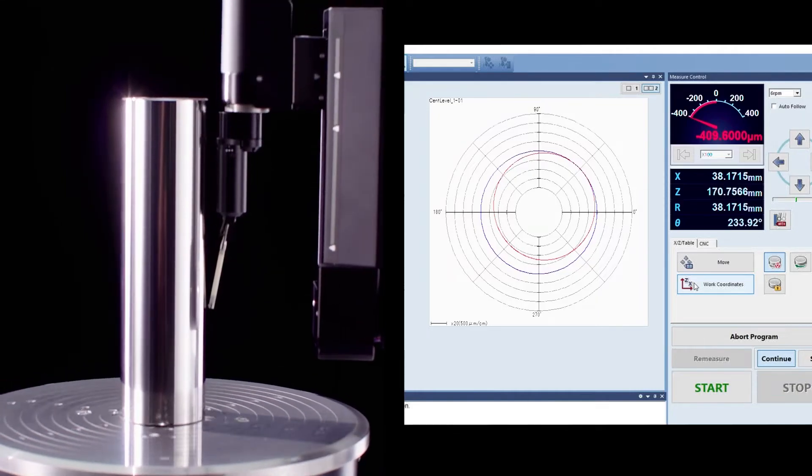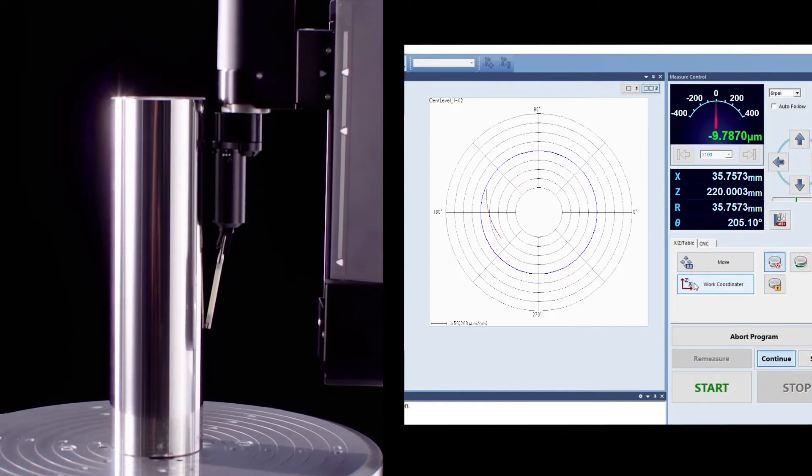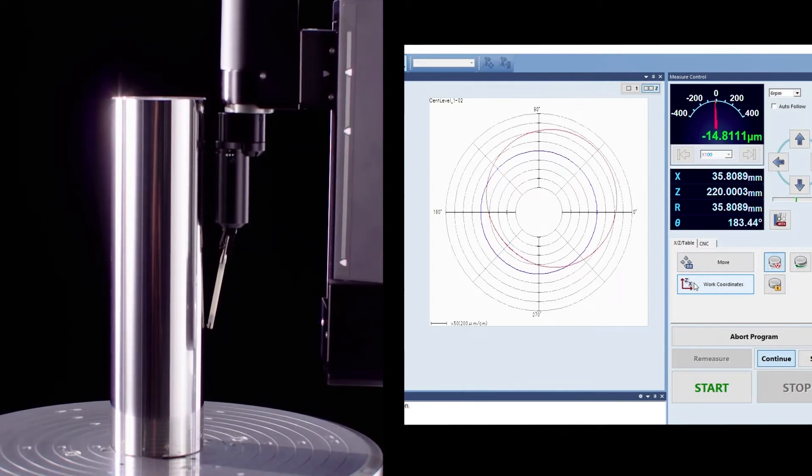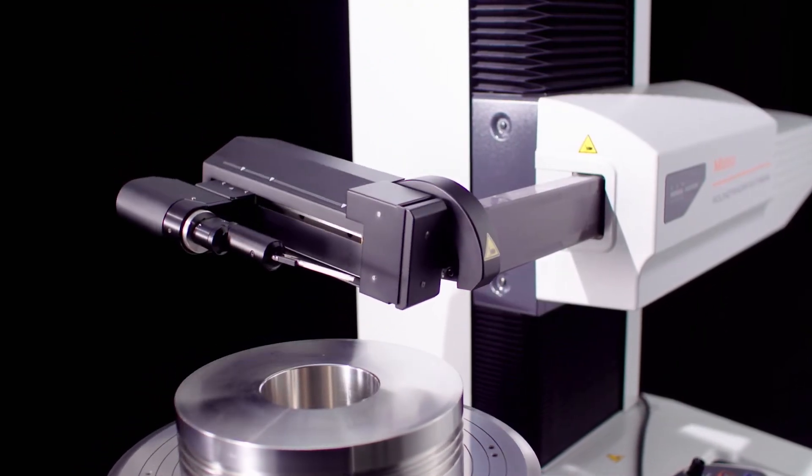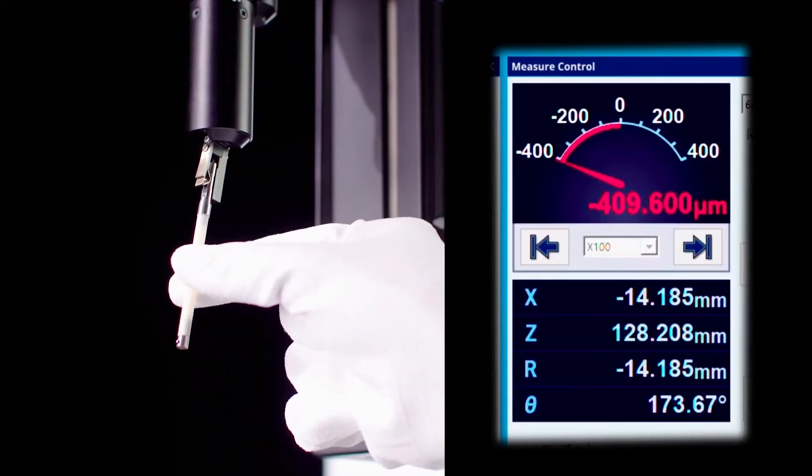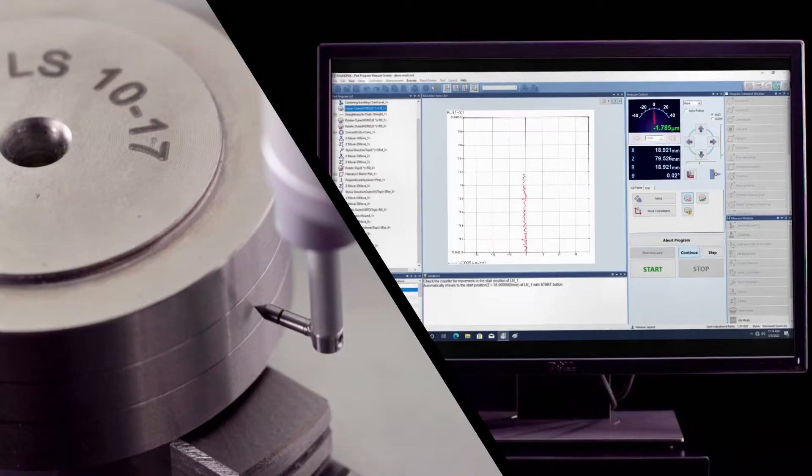Furthermore, it can also be programmed to perform continuous automatic measurement such as squareness and run out by combining inside diameter and upper surface measurements by changing the detector and its holder orientation. An added function in the software automatically detects a change in the stylus angle and recognizes it.